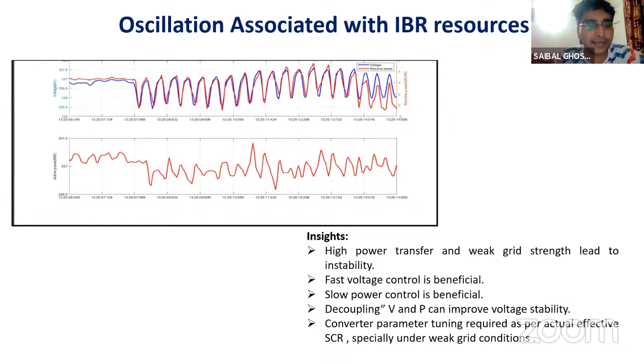Monitoring of oscillation - I already told you that using PMU we can monitor the oscillations. SCADA data, it is very difficult. PMU in the Indian system has a reporting frequency of 25 hertz - that's what we can see at the control center. So theoretically we cannot visualize any oscillation beyond 12.5 hertz, that is half of the reporting rate. But practically, anything above 8 hertz is difficult to see.